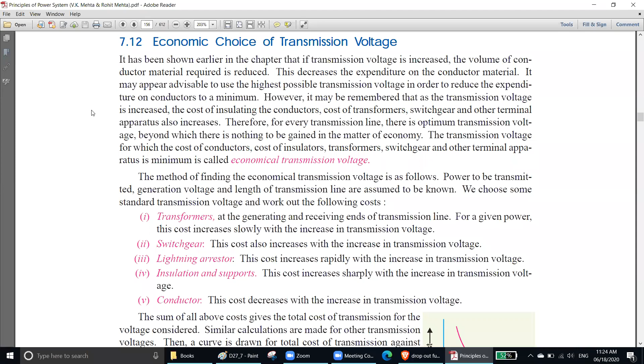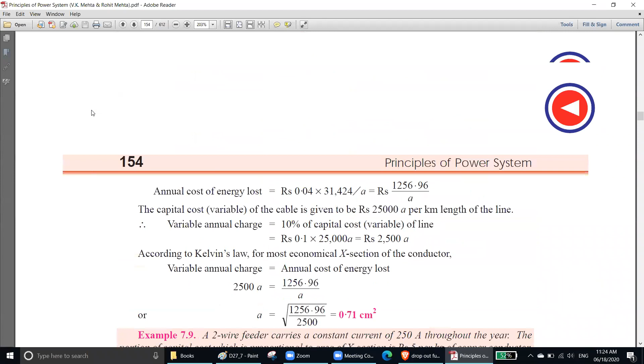Yeah, okay, now this is a very interesting topic, because if your voltage is bigger, that means you need less current, your current will be smaller. Why is your voltage bigger? Because you are using a bigger transformer, it is increasing the voltage and reducing the current. Understood? For the same power, it is increasing the voltage and reducing the current. When the current is reduced, that means it has less amount of voltage drop in your power line. We have already discussed this mathematically, let's go and find out that.